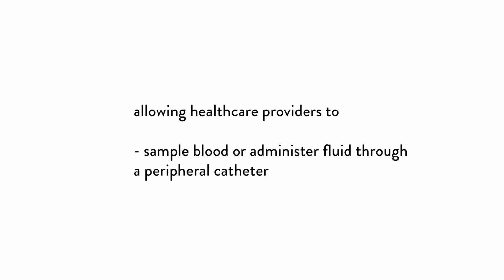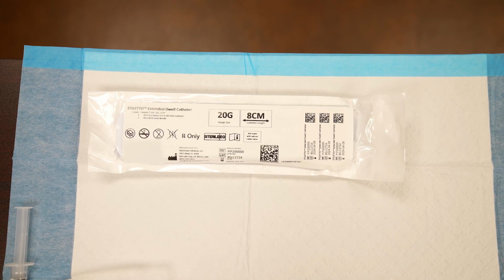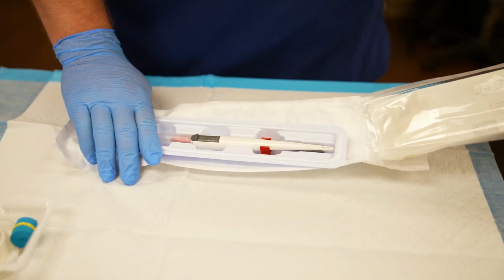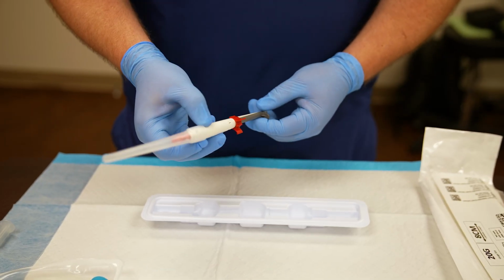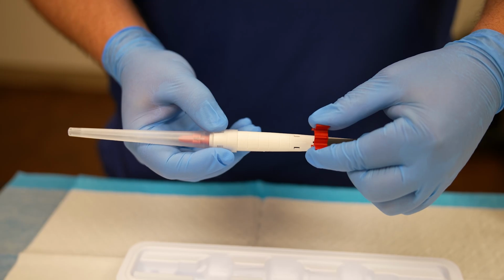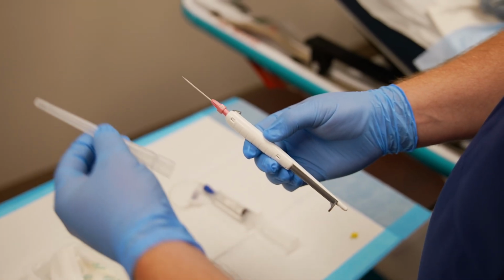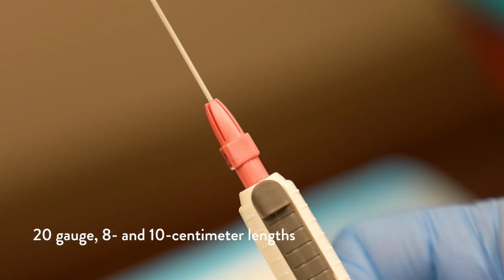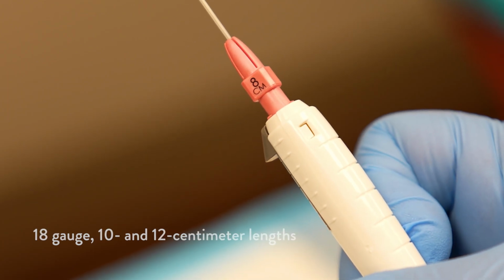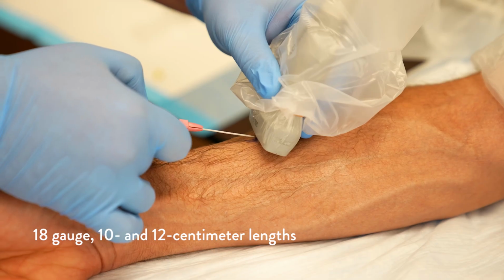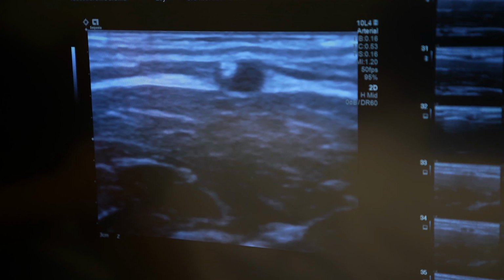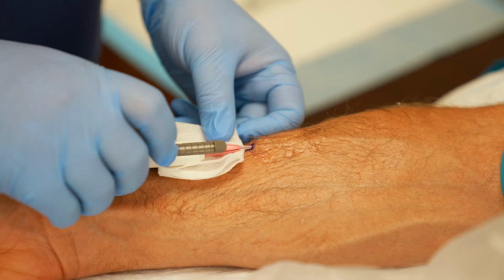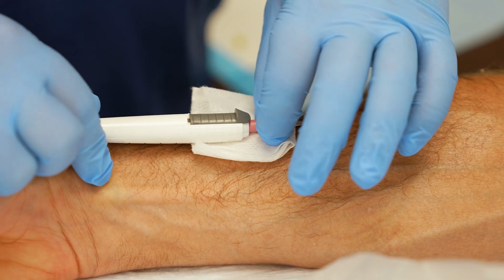The Stiletto is designed for short-term use, up to 28 days, allowing healthcare providers to sample blood or administer fluids through a peripheral catheter. This advanced device supports the use of a single-lumen, power-injectable catheter that can be easily inserted into peripheral veins. The Stiletto comes in two sizes: a 20-gauge catheter with lengths of 8 and 10 centimeters and an 18-gauge catheter with 10 and 12 centimeter lengths. It is suitable for power injection, allowing for precise administration while providing comfort and ease of use.